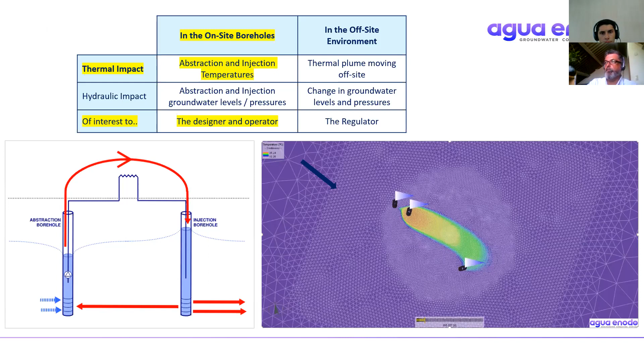A point worth making is that you switch the system on, but it may take many years. You can see the graph on the bottom - this is a strongly cooling-dominant system based on that annual plot shown earlier. The graph above is a 35-year model run, showing how the heating and cooling load makes the temperatures go up and down. It actually takes 30 years for this system, operating as designed, to reach a dynamic equilibrium between the abstraction and injection temperatures.